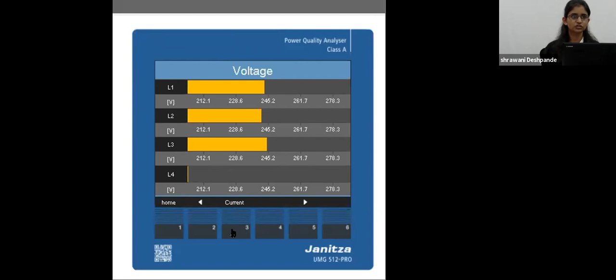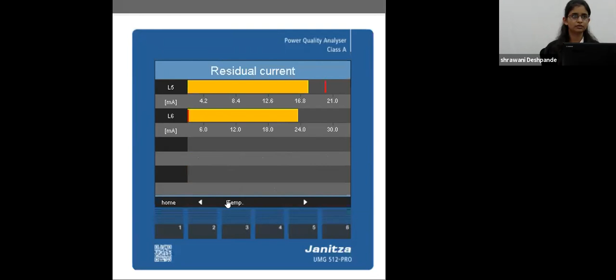Then next is the flicker. As I said, this meter complies to various standards. Therefore, it also complies to IEC 61000-4-15, which is the standard for flickers. This standard defines flicker and some limits for short time flicker and long time flicker. So our meter is capable of measuring short time flicker and long time flicker. Then this is another way of data representation, where we can see all the parameters: voltage, current, real power, residual current, and temperature also.